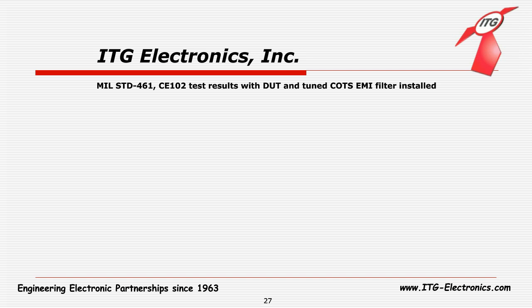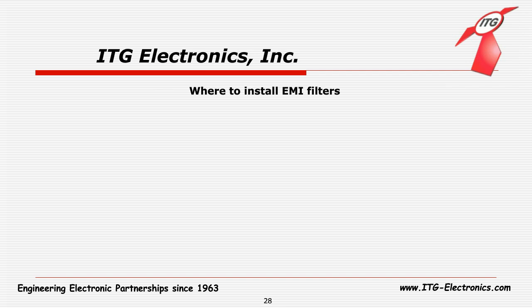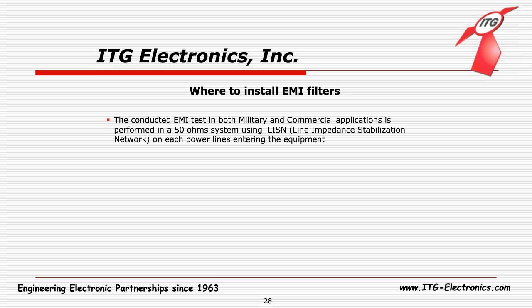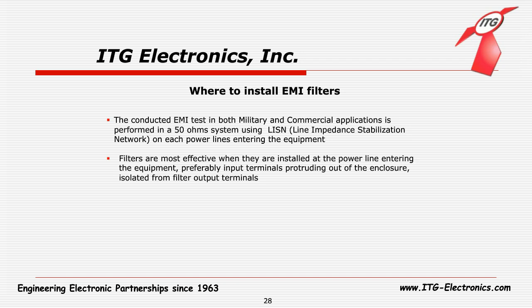One other thing that I would like to mention is where to install a filter. Now, the conducted emission test in both military and commercial applications is performed in a 50-ohm system using a LISN, line impedance stabilization network, on each power line entering the equipment.